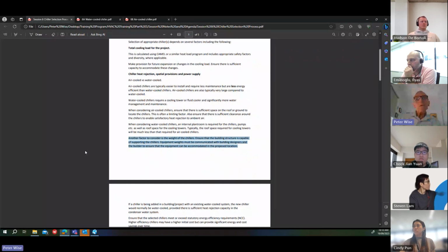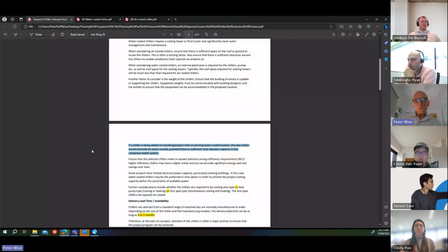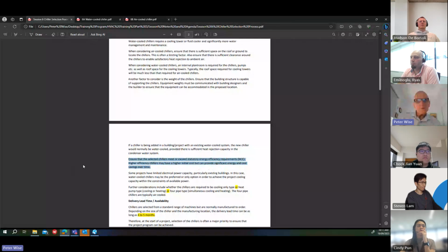Ensure that the selected chillers meet or exceed statutory energy efficiency requirements, i.e. the NCC and MEPS. Generally they will, but if you're using reputable manufacturers, they'll be designed and manufactured to suit those requirements, but you need to make sure they do. Higher efficiency chillers may have a higher initial cost. You don't get something for nothing, so if you're getting higher efficiency, it's going to cost some more money. But they can provide significant energy and cost savings over time.